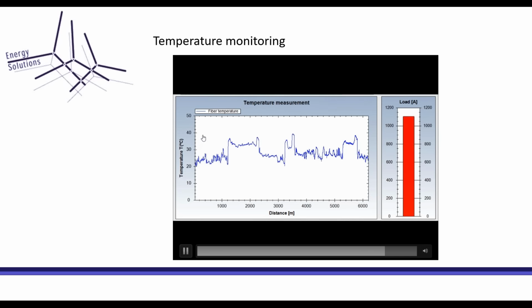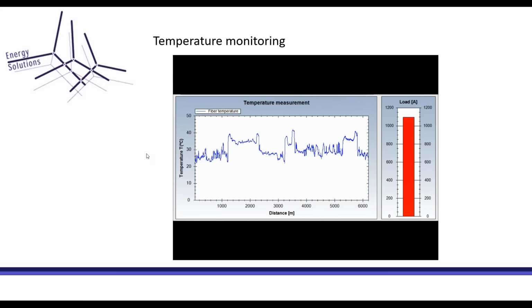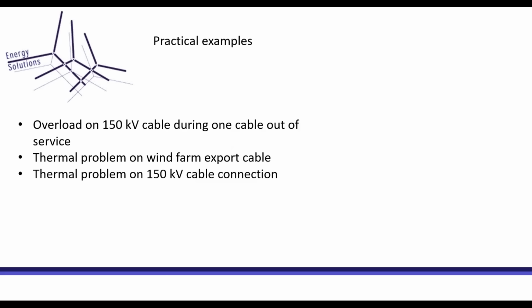Distributed temperature sensing is already quite a known technology and is used for a very long time now. This example is already almost 10 years old. And in the last few years, we've seen some examples where it really has been useful to use dynamic cable rating in underground power cables. So I would like to just briefly go through 3 of the practical examples we have experienced. One is on an overload on a 150 kV cable during a fault on another cable.